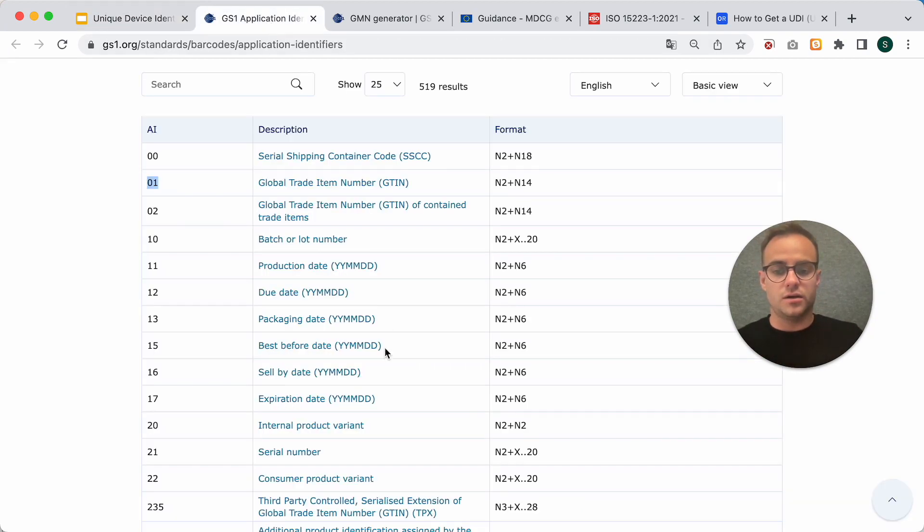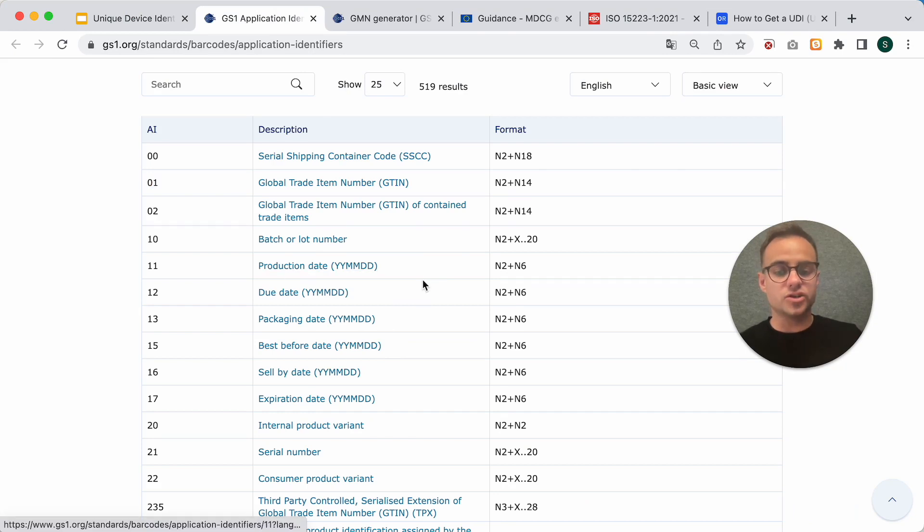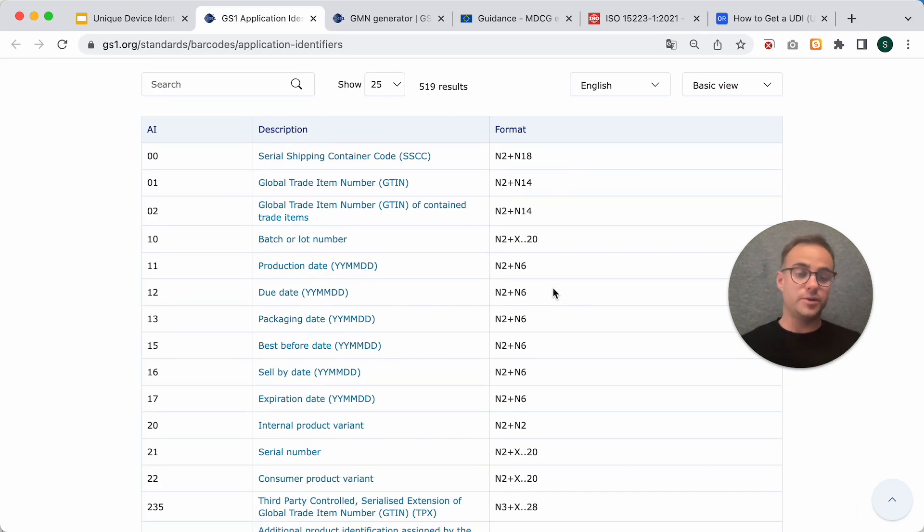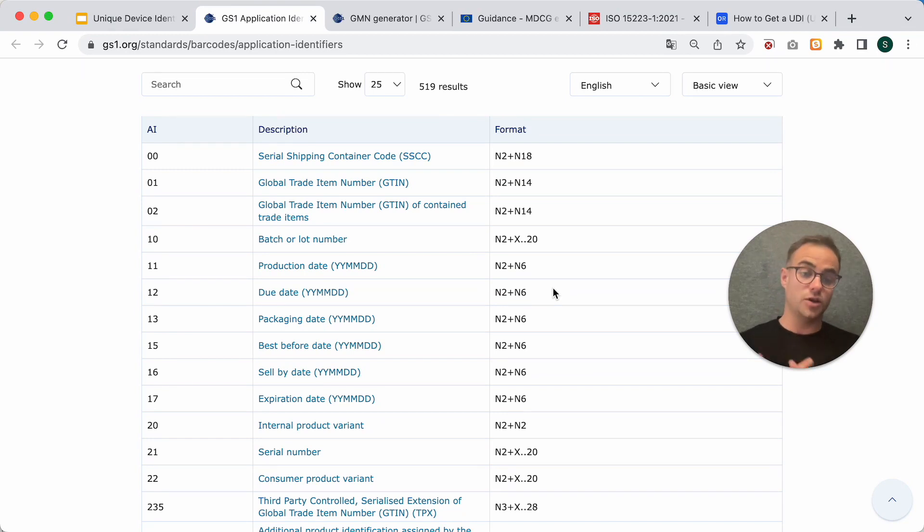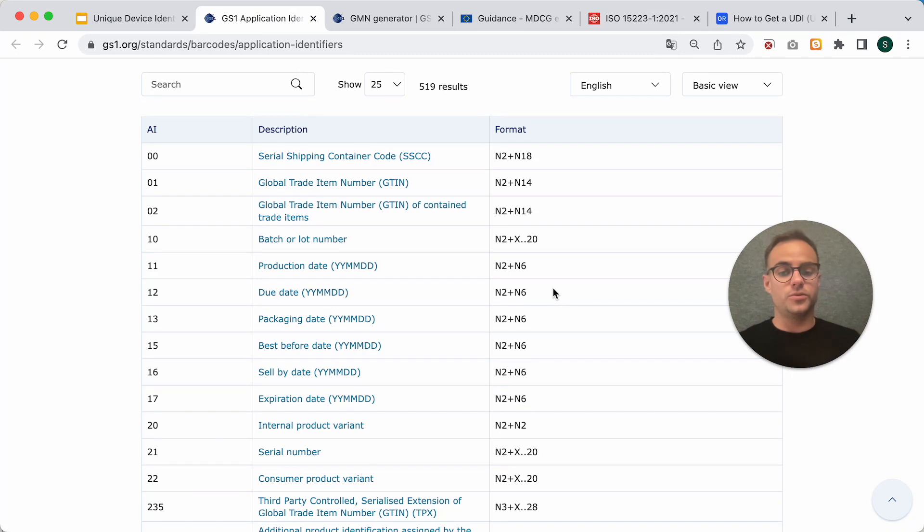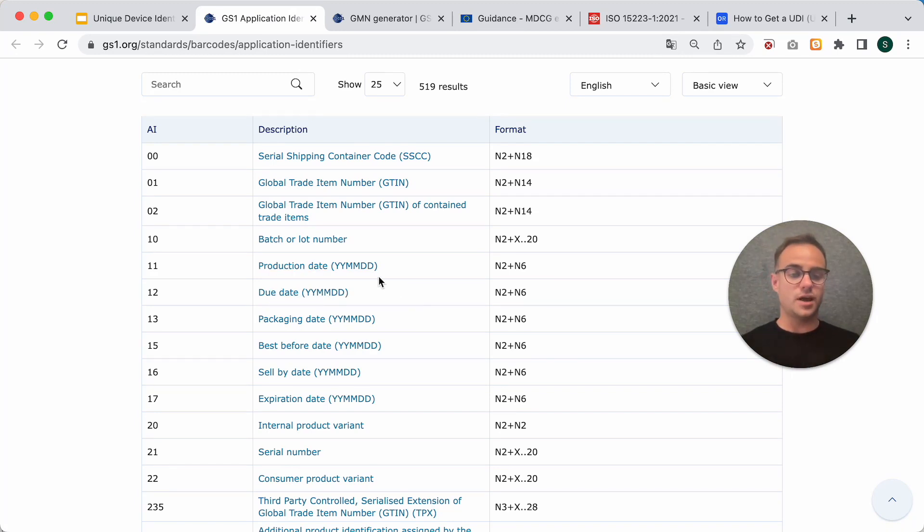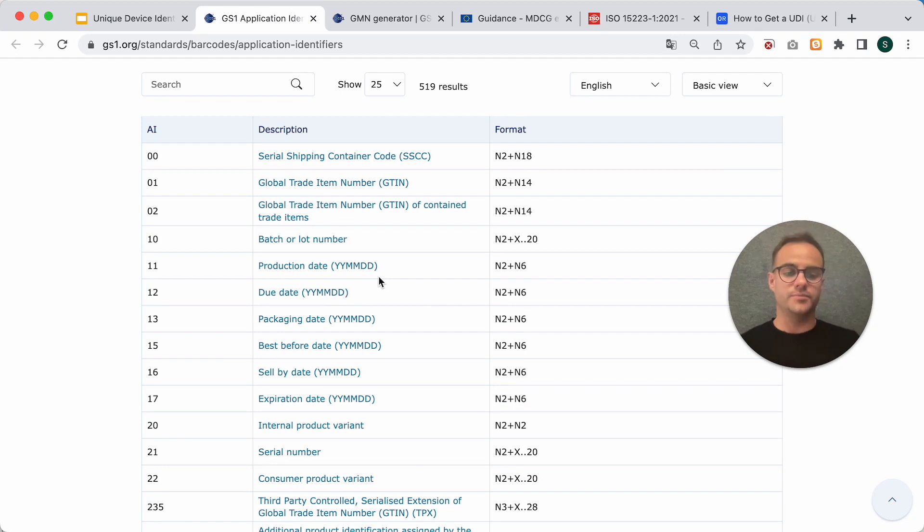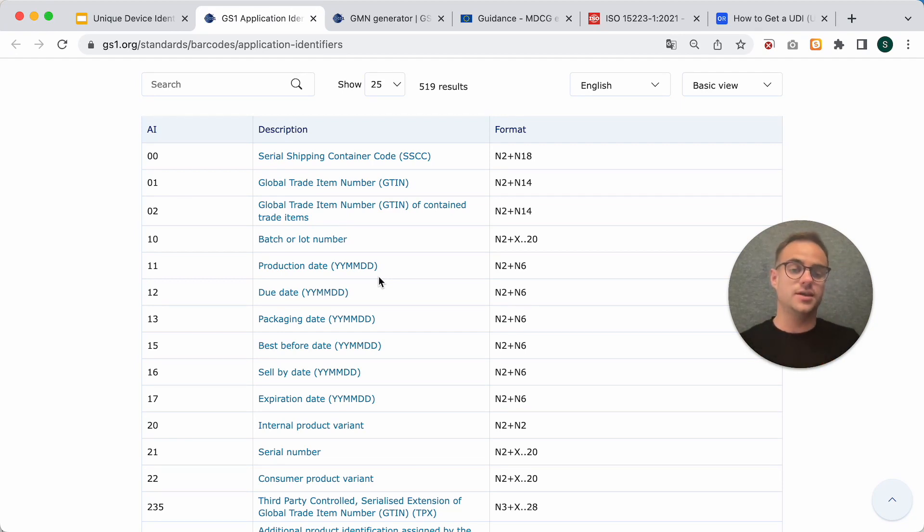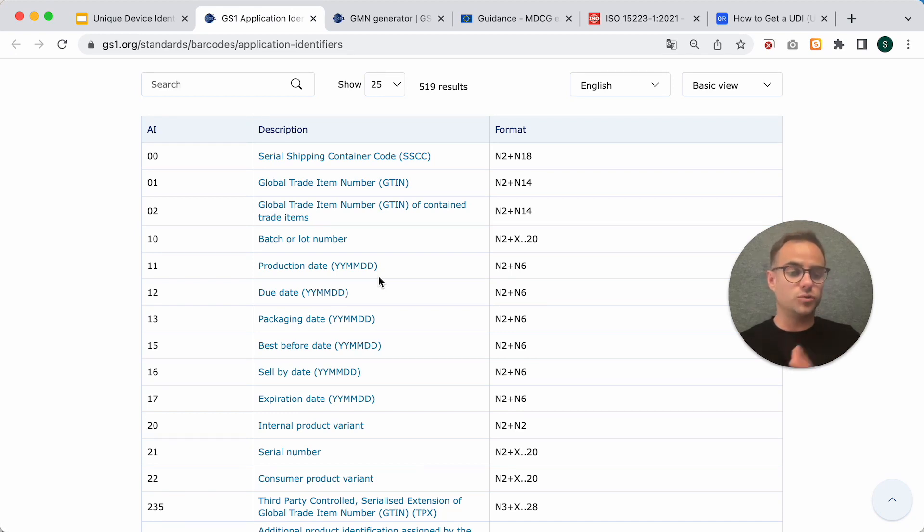All right. Production date as a UDI-PI mostly makes sense if you have a cloud-hosted software medical device where your production date changes every time you make a patch. Because you basically have only one product and everyone accesses it. And the only distinction between your products is the production date.